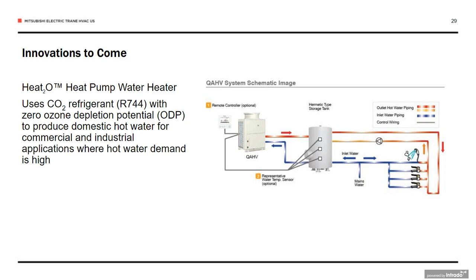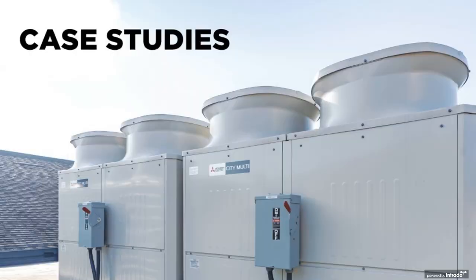And so when you're connecting it to generate a building's hot water, you can connect up to 16 modules of these to a modular tank or a holding tank to generate over 2 million BTUs of heating capacity. And so the water typically is going to come out 160 degrees or higher for that domestic water usage.